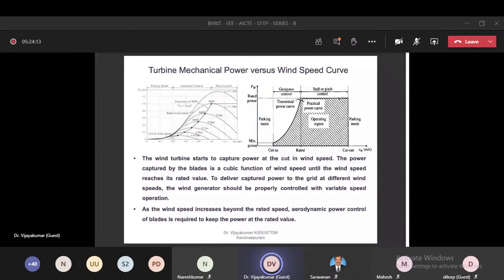So here they will use the pitch angle control to control the speed of the turbine, because the region from 15 meters per second up to 25 meters per second, the cutout speed, is where you can use the pitch control. Because the power output is constant here, even if your response is slower, it doesn't matter, right? So that's why they use the pitch control to control the turbine. After the cutout speed, normally they stall the turbine. Stalling the turbine means they stop the turbine from rotating. Why? Because high wind speed can damage your turbine. So once it reaches the cutout speed, 25 meters per second, they will stall the turbine. After that, that's parking, right?